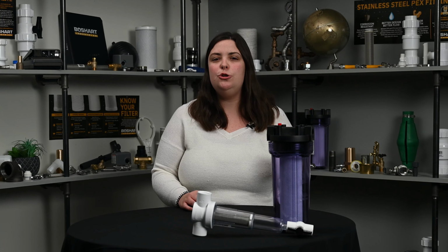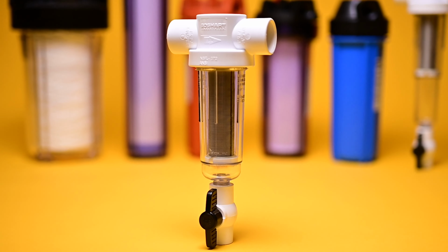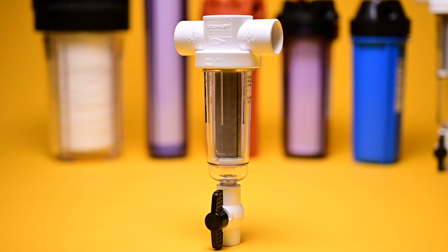So, pre and post filtration. This type of filtration is generally used before other filtration systems such as reverse osmosis or UV. These types of systems need the water to be filtered to a certain level before they can remove bacteria from the water. If there is too much sediment going into a UV system, it will not properly filter the water, as the bacteria can hide in the sediment. This is where a pre-filter system would be used. If you are using an RO system, having a pre-filter will ensure that your filters stay cleaner longer, which will save money on filter purchases.